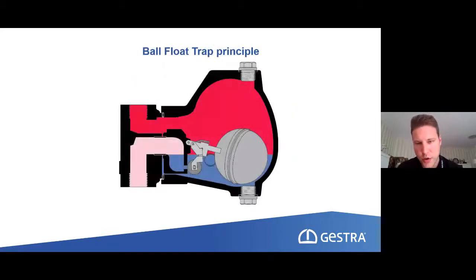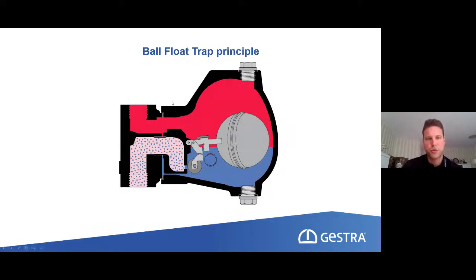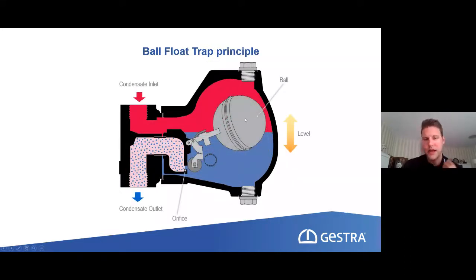If we take a look at the design, how it looks nowadays, we see here how the principle works. So condensate is entering, it gets more and more, and the higher the level goes, the more of the orifice will be opened. And then you see how the condensate will be discharged here. And here we see a very specific phenomenon now. As soon as we have this very hot condensate being reduced in pressure, we will create so-called flash steam. So after the steam trap, when it opened, we will not have only condensate, we will have condensate and small amounts of steam.